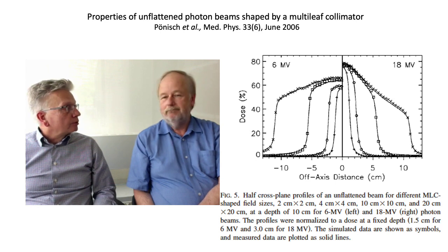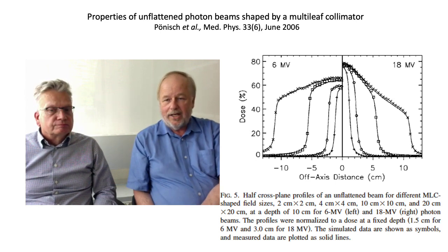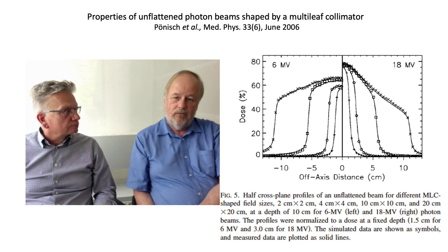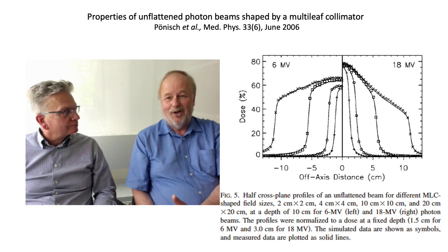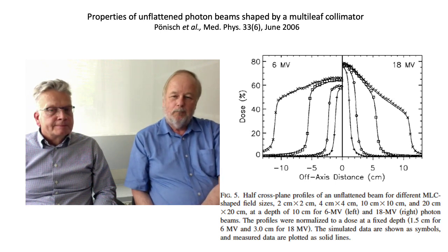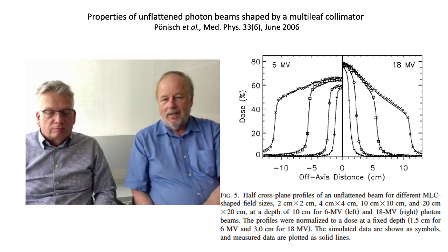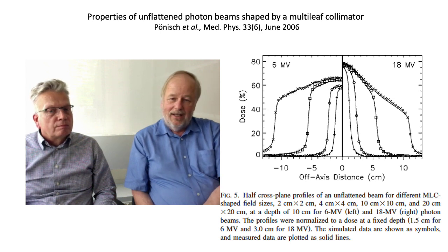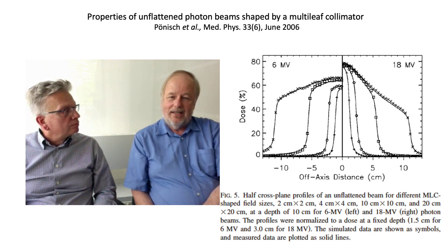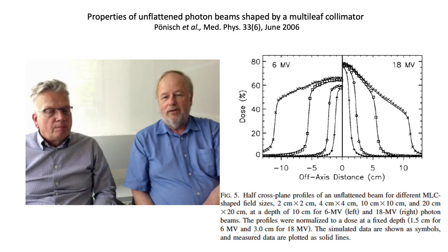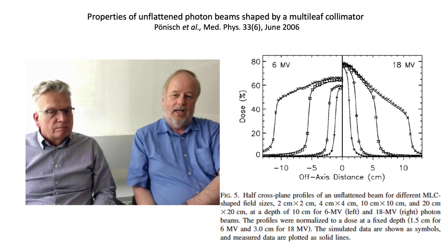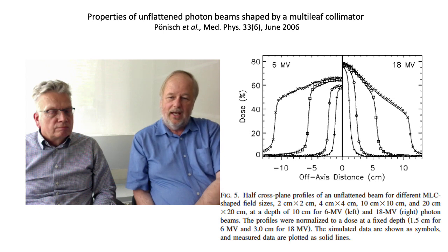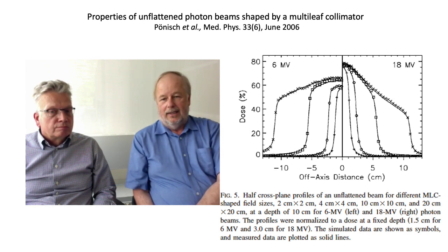Tomotherapy used the same idea. Actually, Accuray had the first flattening-filter-free design, but with a relatively small field — tomotherapy was the first to really use this on a larger scale. And you can use it as a spectrometer too, because if the energy of the LINAC changes, the angle will change, and it's actually easier to detect energy changes by the change in angle with a good detector than by doing a depth-dose curve.